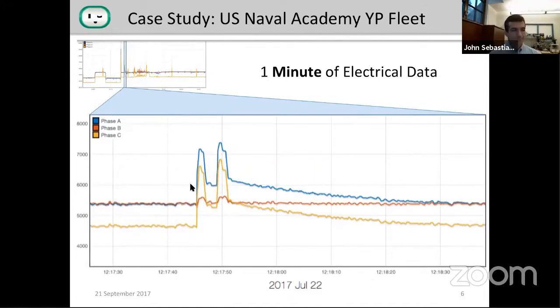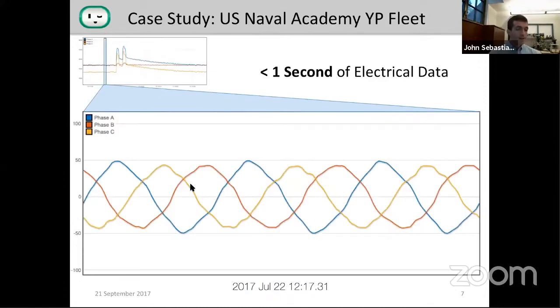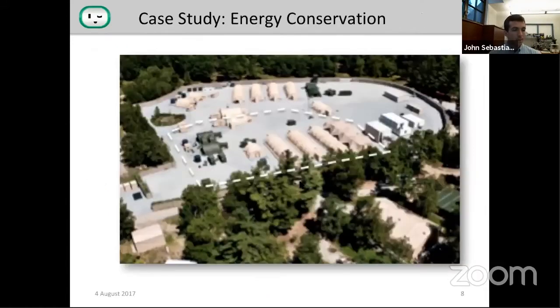We can even go down to sub-line-cycle resolution, where you can actually see the harmonic characteristics of the current. This can help the crew diagnose issues with poorly performing generators or power electronic loads that are hurting the ship's electrical system—quite a lot of information, just from a few magnetic sensors zip tied to the outside of the power line.